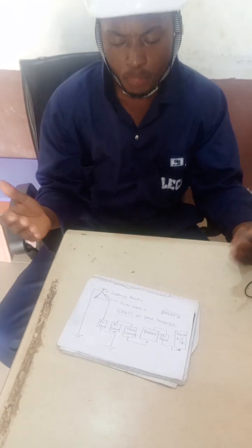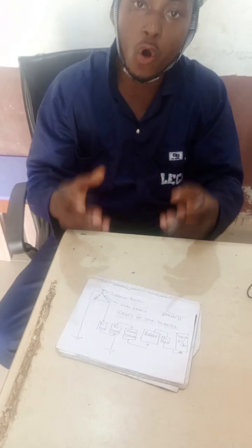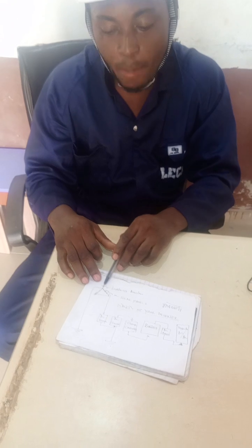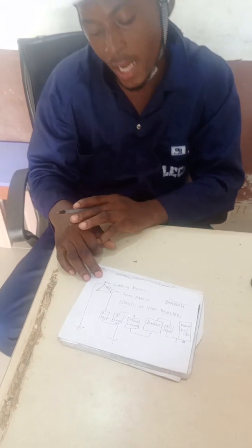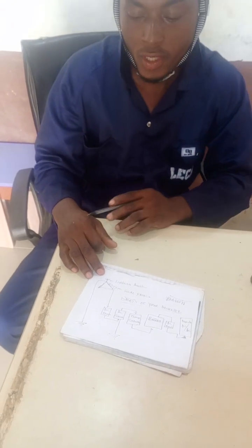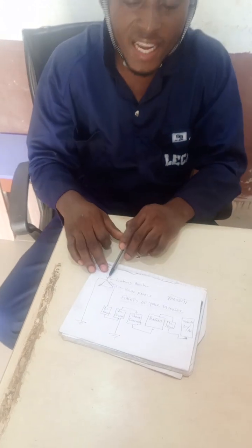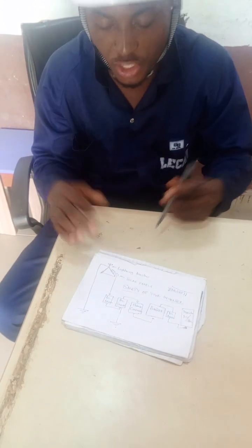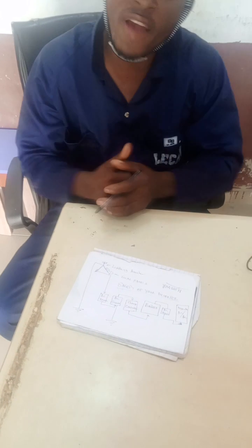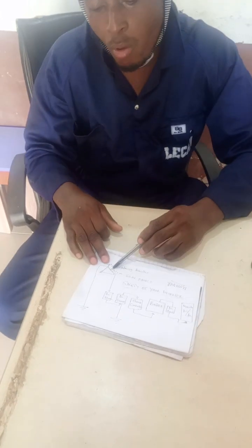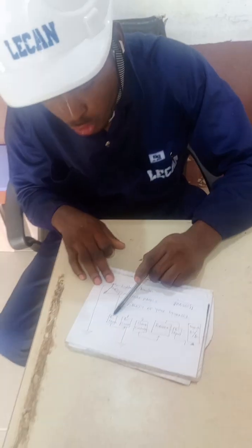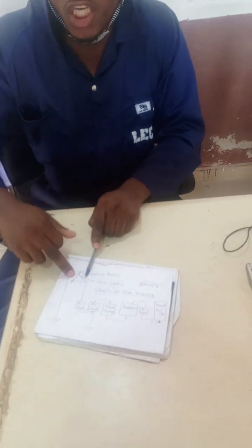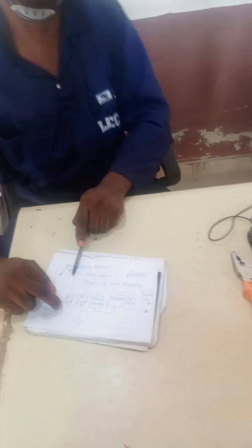Now, let's assume that the way the lightning struck your building, it is able to bypass the lightning arrestor. Or let's assume the lightning arrestor did not absorb all the charges from the atmospheric discharge. Let's assume some of the high voltage moved to your system. The moment it moved what? To your system, that lightning can pass the DC breaker. If it passes the what? The DC breaker, it will now go to what?